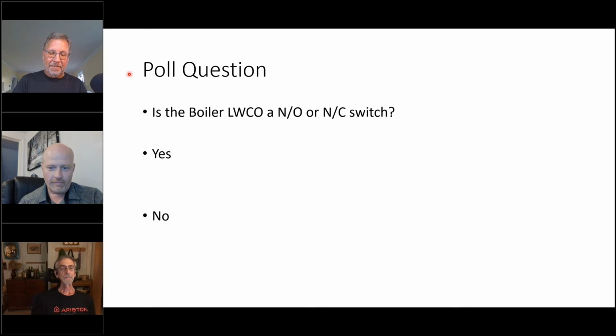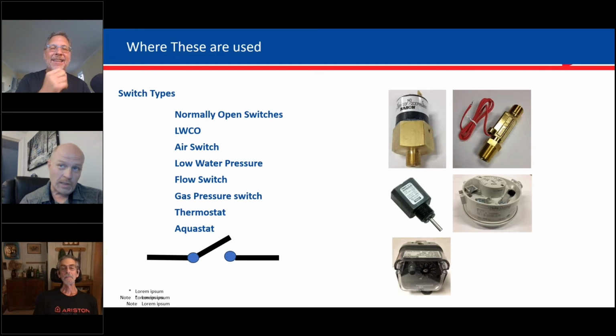Good question. That is a good question, because think about this. What does the switch do when you set it on your desk in front of you? That is kind of how I look at it. Well, think of this. For all those years, we told everybody not to put Teflon tape around the brass probes, because the brass probe with a low water cutoff allows continuity to be sensed back. We're actually going to go over how the low water cutoff works, or at least the one that we use, later in the presentation.